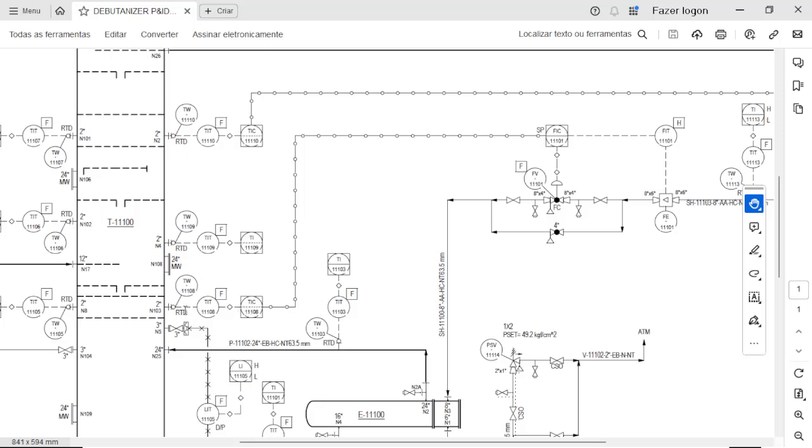In this case here, we have the electrical signal from the instrument to the transmitter, and the transmitter sends a signal to the controller, and as both of them are in the control system, we will not send the signal as an electrical signal, but as a digital signal. So it means that the interface between the field and the control system is done by electrical signals, but the interface between different components or control loops inside the control system is done by digital signals.